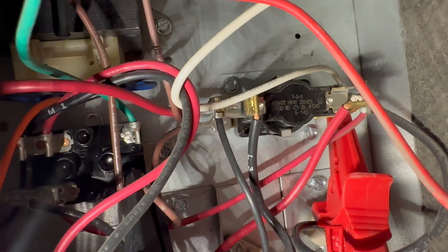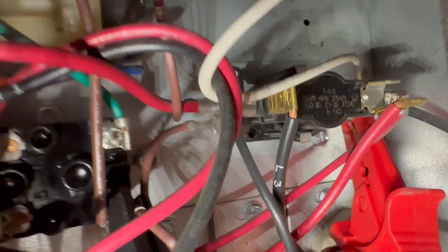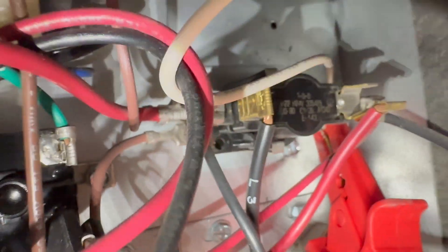Now with the power still off I'm putting one clamp on this heat sequencer at the bottom. The bottom of the sequencer is the 24 volt coil. My other clamp is on the brown wire which supplies the low voltage to the other side of the coil.